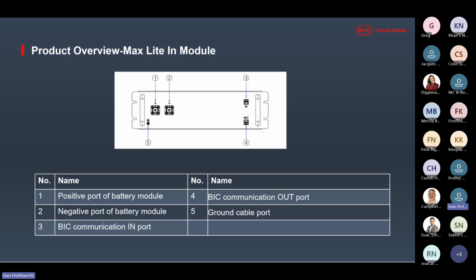And here we can see just a very brief rundown of the module itself. Sometimes people have to install batteries with a rack that's not manufactured by BYD, as they installed third-party racks. And then it's always recommended to use the earth connection on the batteries. The batteries and the PDU, which is the connector at the top, and then all the battery modules always have to be earthed in order to ensure good communications and safety.